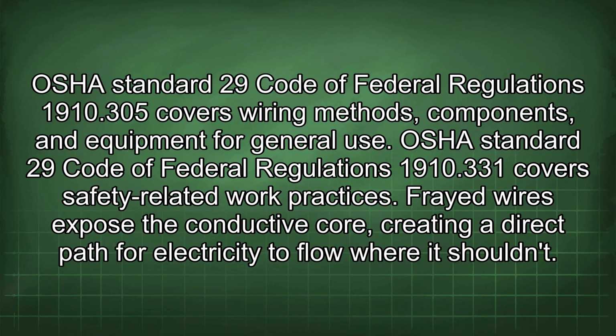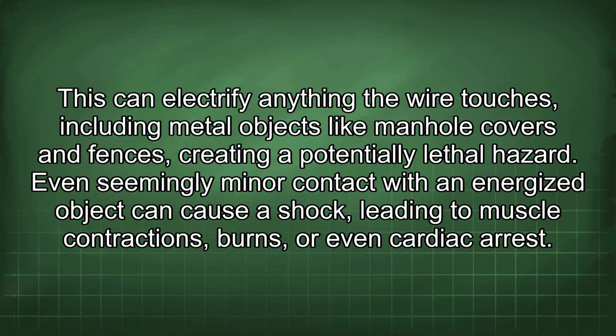OSHA Standard 29 Code of Federal Regulations 1910.331 covers safety-related work practices. Frayed wires expose the conductive core, creating a direct path for electricity to flow where it shouldn't. This can electrify anything the wire touches, including metal objects like manhole covers and fences, creating a potentially lethal hazard.